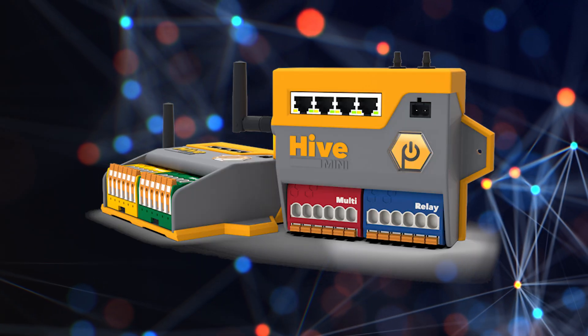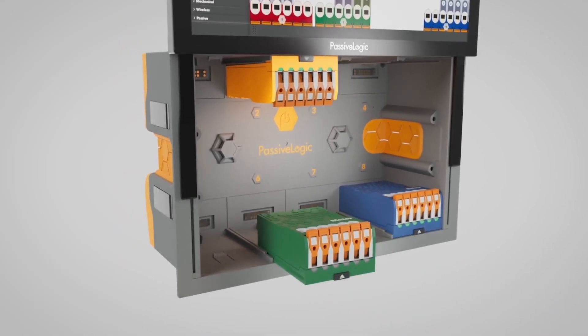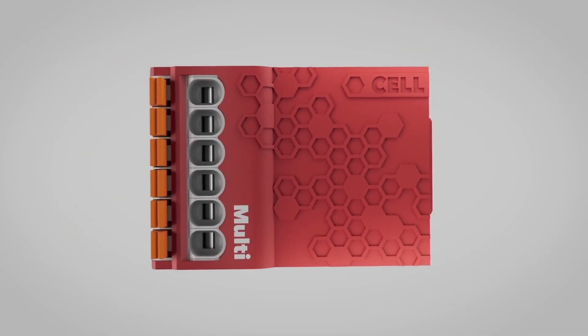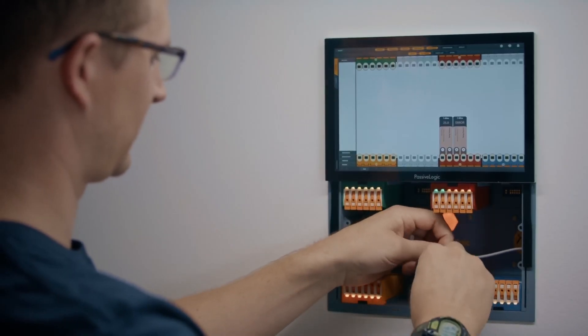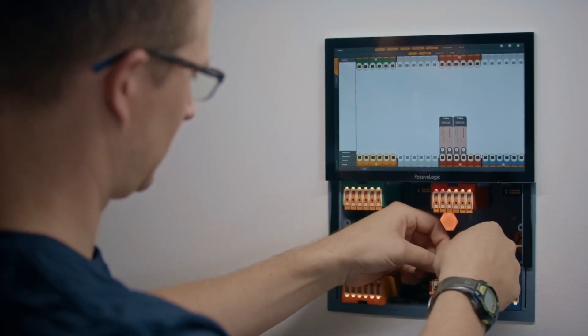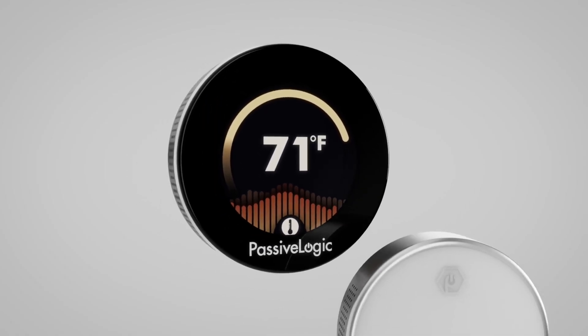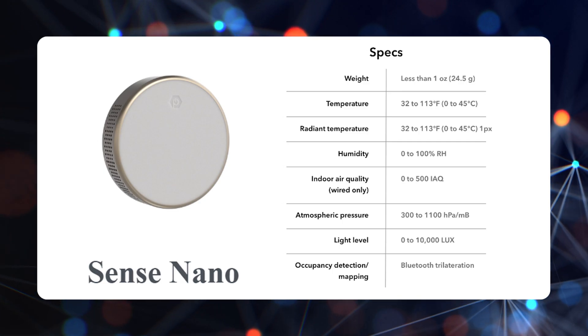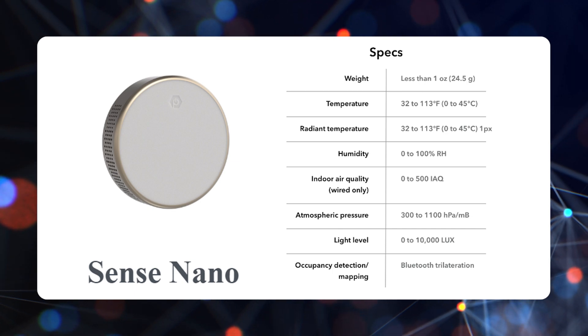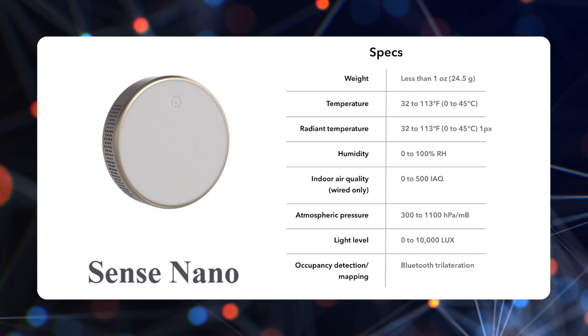The next hardware device is the Hive Mini, which doesn't have a touchscreen — it's more for boosting existing wireless connectivity and making installation more flexible. Within the Hive or Hive Mini are the cell modules — four different modular devices for input and output that connect wiring for all the different devices in the building and control and measure the devices connected to them. PassiveLogic also has two hardware sensor devices. The more sensors you have in a building, the more accurate the digital twin will be. They created the Sense Nano and the Sense Touch. The Nano has seven sensors: air temperature, radiant temperature, humidity, air quality, light level, air pressure, and occupant location services.